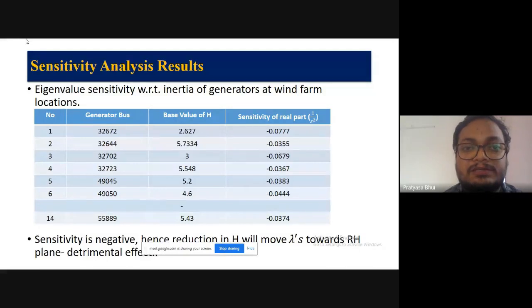So at each generator bus, basically where a wind farm was replaced with a synchronous generator, the base value of H is given. You can see the table. With respect to the inertia of that generator, we are finding the eigenvalue sensitivity of the critical mode. So whether the real part of the eigenvalue is going towards the left half plane or the right half plane. If it goes towards the left half plane, it is going to be more stable, so you can increase generation. But if for a critical mode the real part is going towards the positive half plane, that means your damping ratio will become poor, and your damping will become poor, so you cannot increase renewable generation at that location. So we'll do the eigenvalue sensitivity studies for a critical mode.